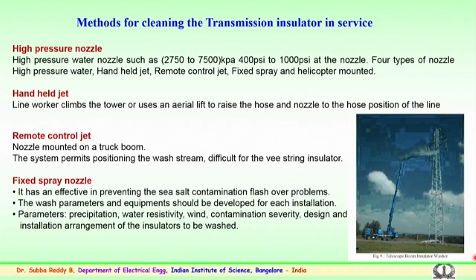The utilities or the power grid normally use various types of nozzle sets, normally of high pressure. These high pressure water nozzle sets should have a capacity of 2750 to around 7500 kilopascals, with 400 psi to 1000 psi at the nozzle. Sometimes these numbers could be slightly reduced in case of traction insulators operating at 25 kilovolts. Again, these traction insulators could be of ceramic or polymer type. Some of the literature mentions 250 psi to 350 psi where it is used, and here 1000 kilopascals to 1250 kilopascals, and so on. So, these are for the transmission insulators.